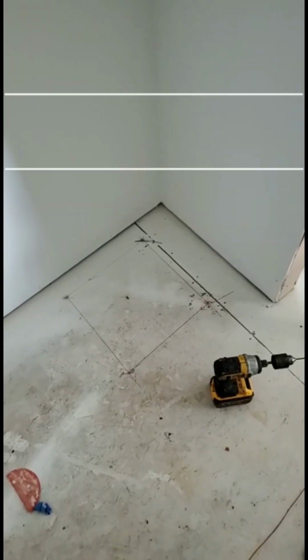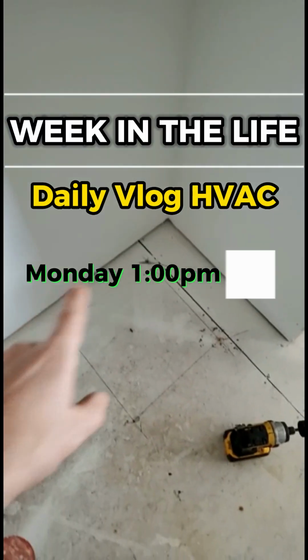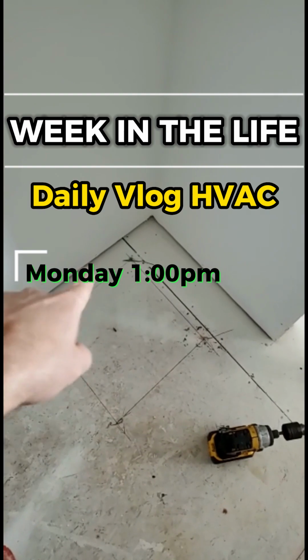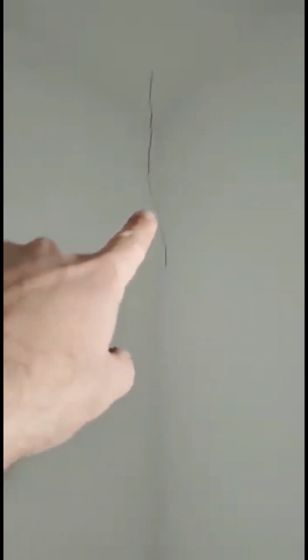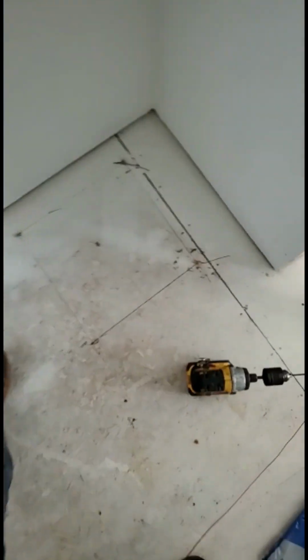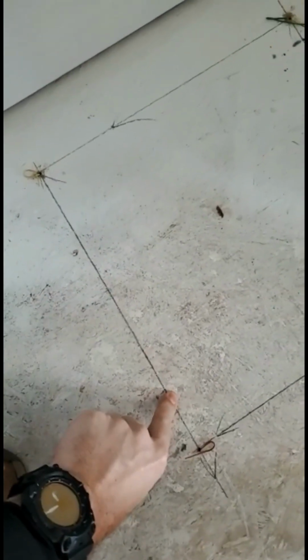Okay, so I'm here today on a new construction job site working on speccing out a 14 by 14 return in the ceiling and in the floor. What I wanted to point out though is the best way to do that, for sure when you're working on the floor, is to look at the joists, see where they are. In this case, the joists run like this, and then I can know that I've got at least 14.5 inches in between them approximately, because they're 16 inch on center.